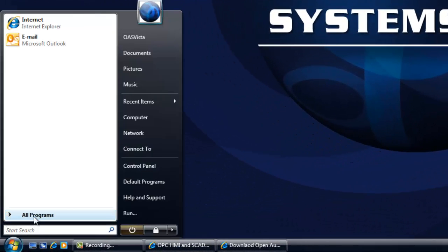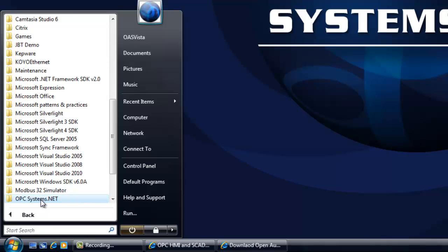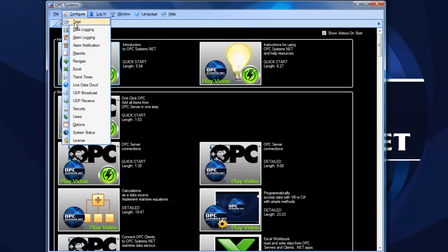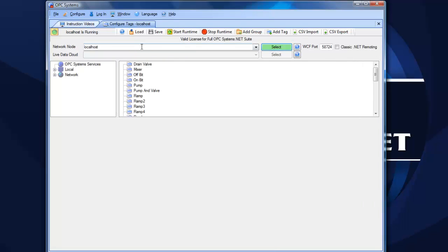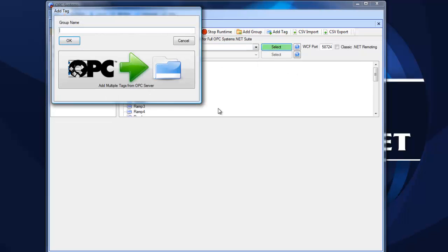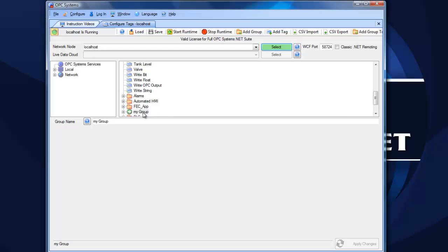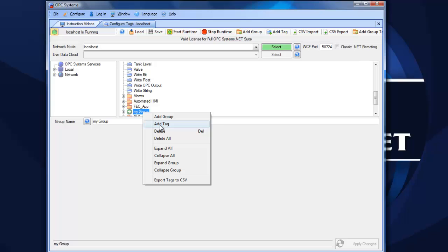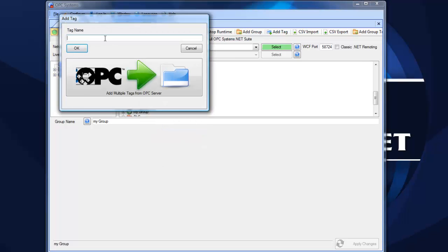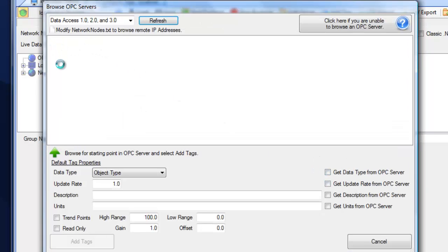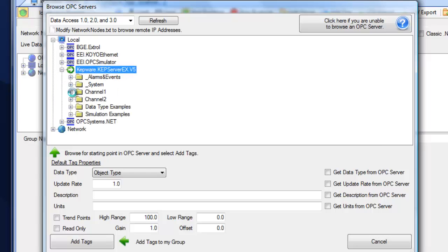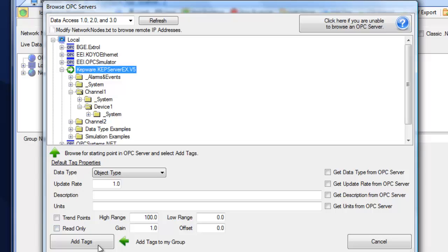To bring in values from an OPC server, select the program group OPCSystems.net and open the Configure OPC Systems application. When you first install, you can run it for a 30-day evaluation with all product features fully functional. Select Configure Tags, then select the local service — note you can also connect to remote services. Add a group to organize your data. Select that group, right-click, and choose Add Tag. You can add one tag at a time or multiple tags. Using the one-click OPC feature, browse to a starting position within an OPC server — for example, the Kepware OPC server — and select a branch or the root to import all items.